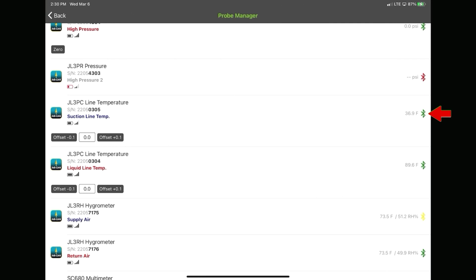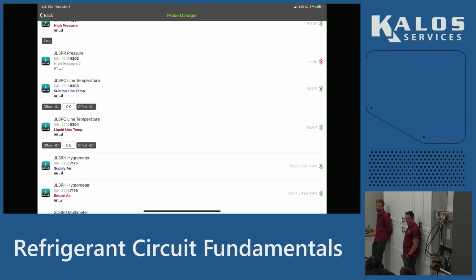I opened a sealed system, right? So now, going over, well, the fan is still pulling air over the coil. It sucks, with less pressure, because it's taking in this air. Before, all the air was forced straight through that coil. Now a big part of the air that the blower can move is going around it. So that means less air making contact with the surfaces of our coil.